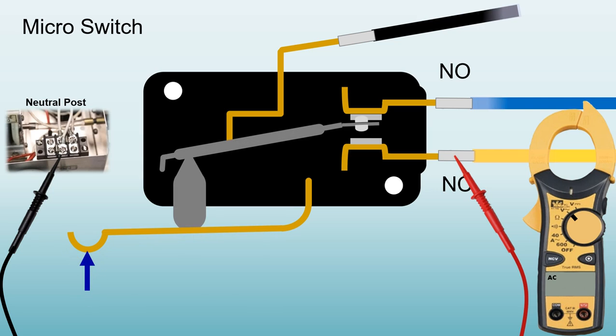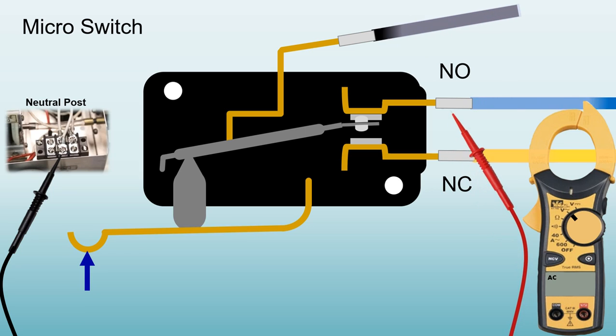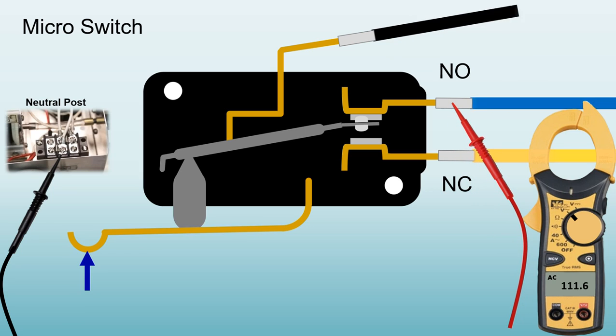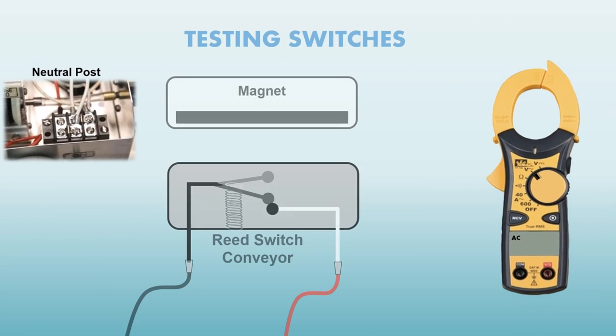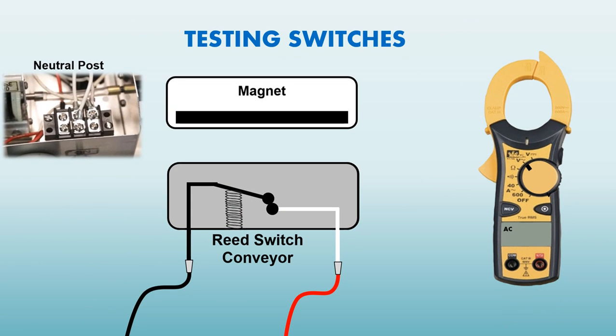If the micro switch has a force against it, or as a Kramer timer is turning, the switch changes positions. We now lose power to the normally closed. We can move our meter lead to the normally open, where power is going to it. Remember, when force is removed, then the switch goes back to its normal resting position, and in this case would be a normally closed circuit.